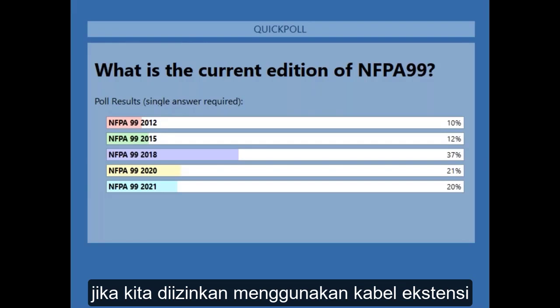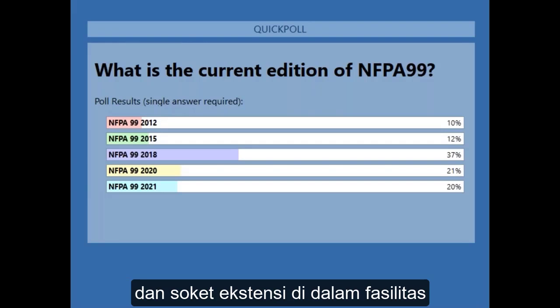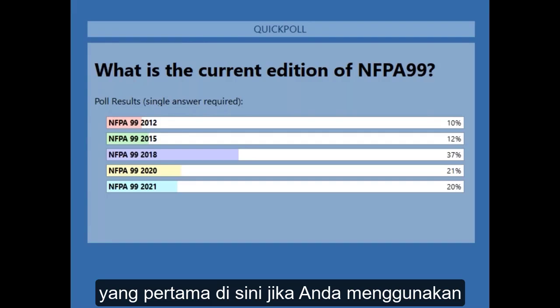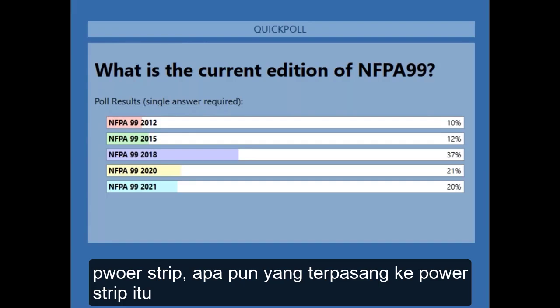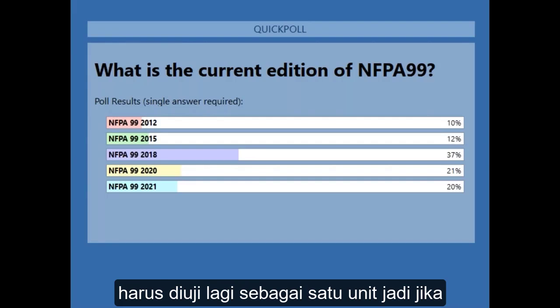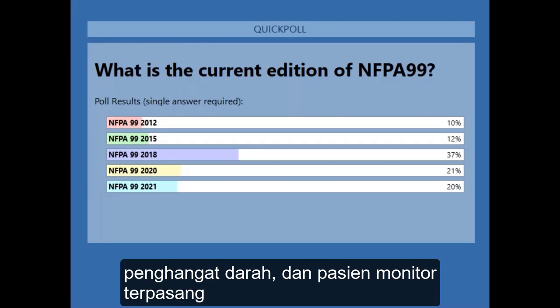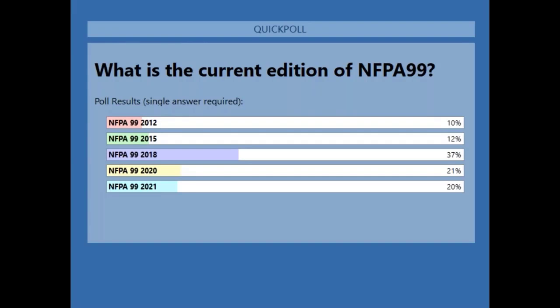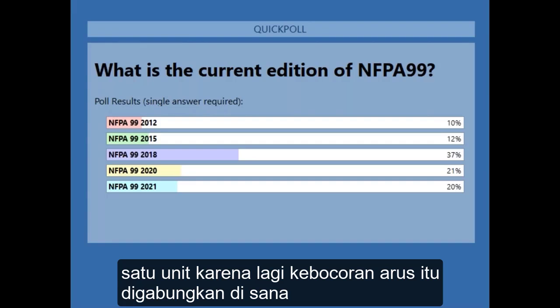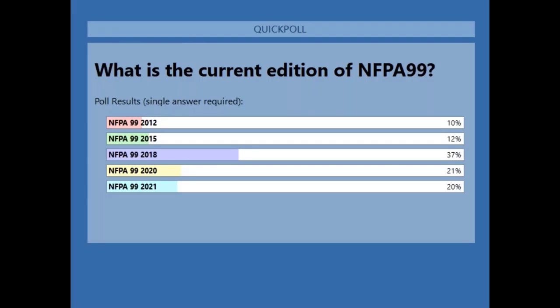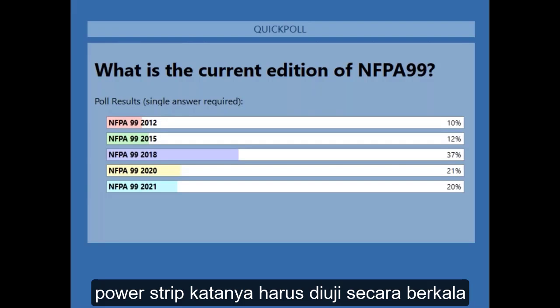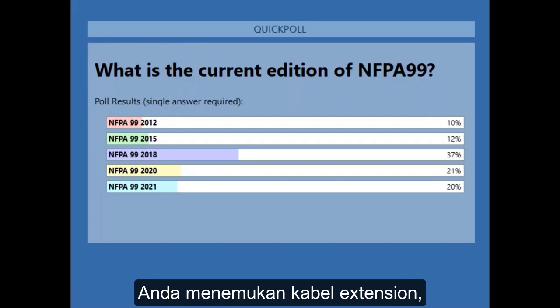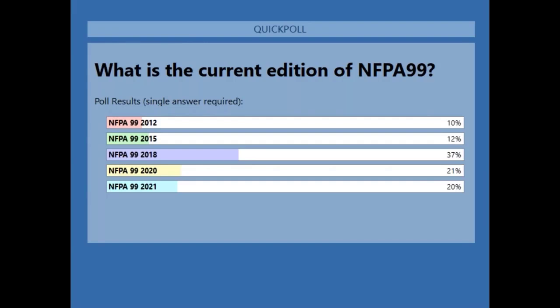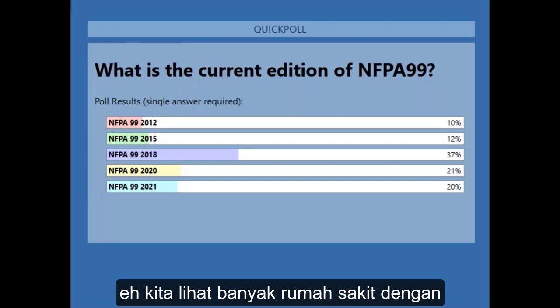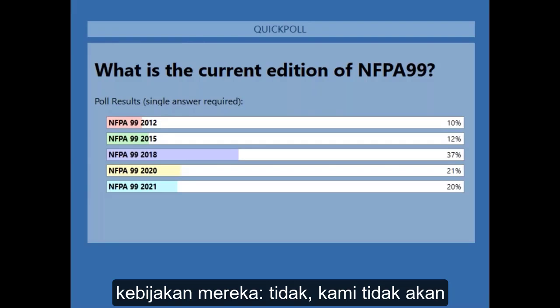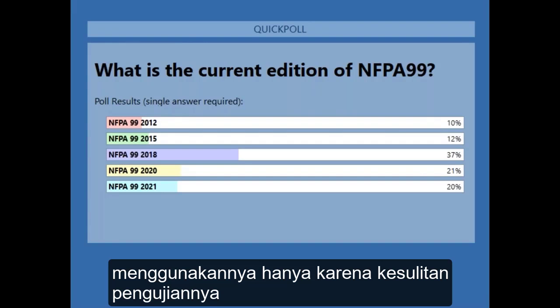Which also brings up another thing: if we are allowed to use extension cords and power strips within the facility. The first one here, if you're using a power strip, anything that is plugged into that power strip must be tested again as one unit. So if you've got an anesthesia machine, a blood warmer, and a patient monitor plugged into it, you are required to test that as one unit because, again, that leakage current is combined. Now, if we do use extension cords or power strips, they have to be tested periodically. The issue is, how in the world do you find those extension cords? How do you find the power strip that's out there? That's a whole other issue. We see a lot of hospitals just say their policy is no, we're not going to use them, due to the difficulty of testing those.